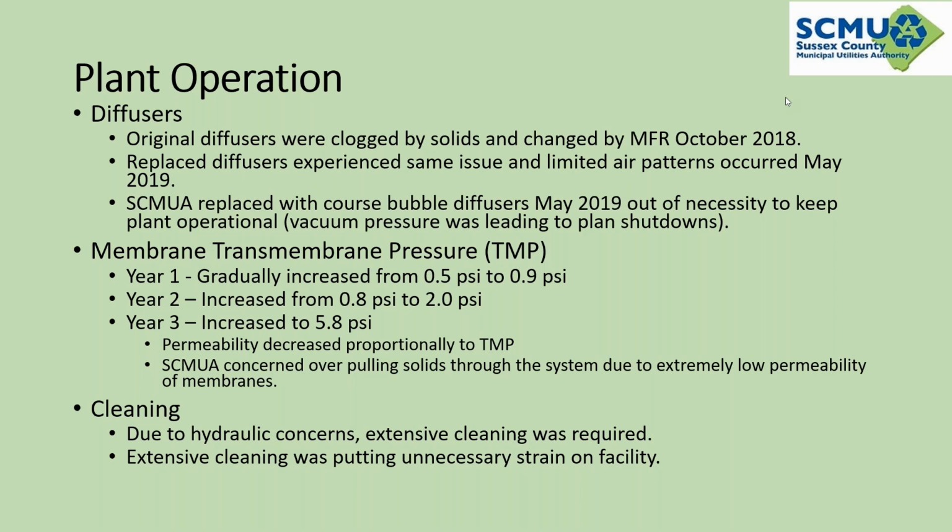This facility was just operational in November of 2016. When you look at the grand scheme of things, if you're looking for a 10-year life, why after just 2 years are you seeing this type of reduction in the treatment capacity? As I mentioned in that timeline, in October of 2018, it was confirmed, really admitted, by the manufacturer that there was a flaw in the original diffusers.